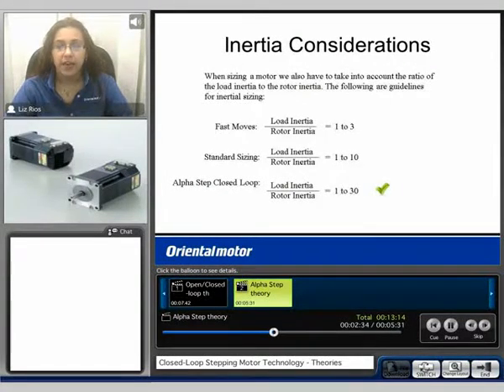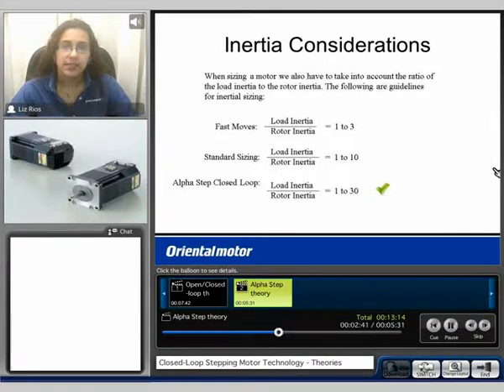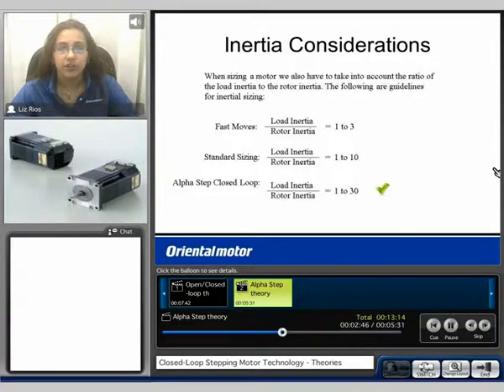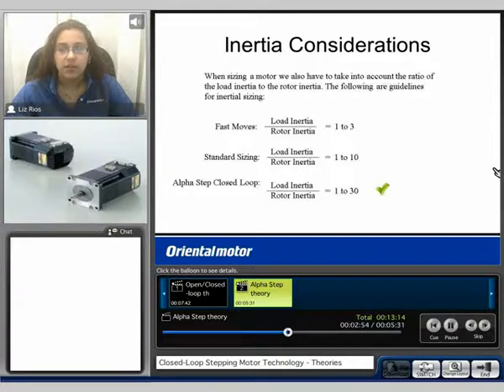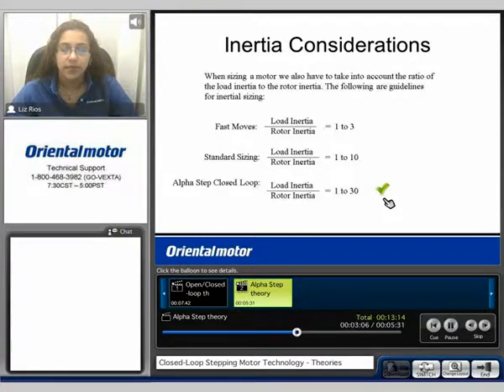When selecting the proper motor, we also have to take into account the ratio of load inertia to rotor inertia. Here we can see some general guidelines used for sizing. For fast moves, your load inertia to rotor inertia can be up to a 1-to-3 ratio. For standard sizing, or for open loop systems, you can have a load inertia to rotor inertia of 1-to-10. And for an AlphaStep closed loop system, you can have a load inertia to rotor inertia of 1-to-30. Therefore, a closed loop system can handle more load inertia than that of an open loop system.